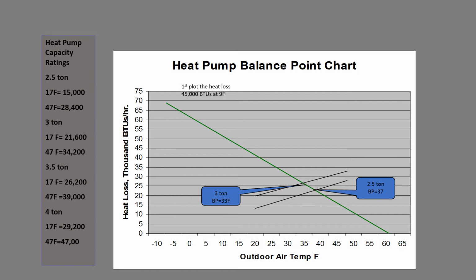The next size up gives you 33. We're getting closer. The 3.5-ton would give you 28. Nice fit. I think that'd be a very nice fit for this house. 4-ton, you're getting down to 25. And boy, you're probably paying lots for that, and chances are you'd probably also have to increase the size of the ductwork to handle that.